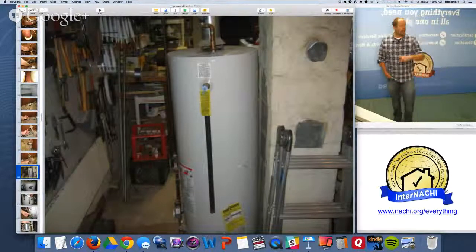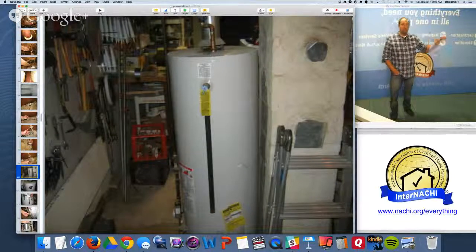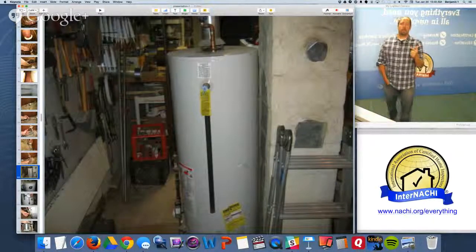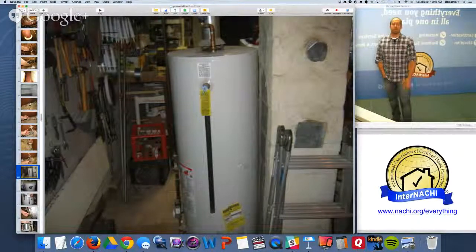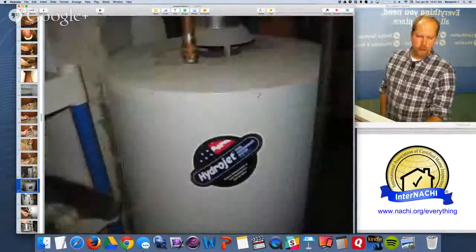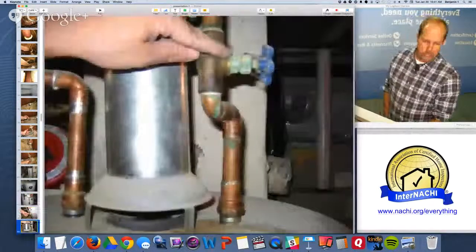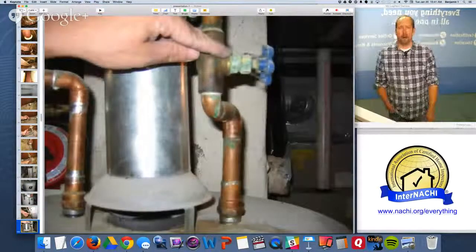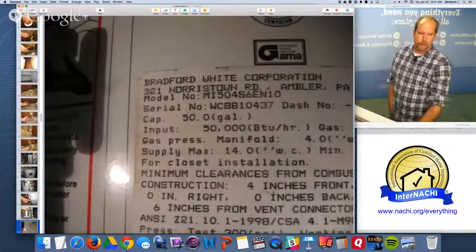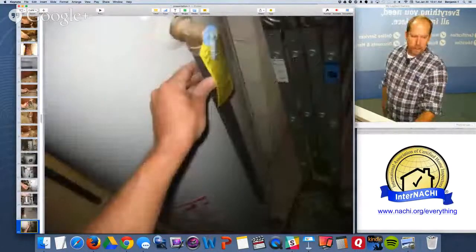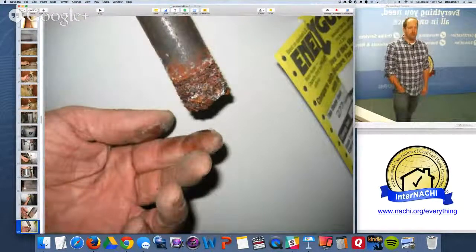There's the natural draft hot water tank, and there's the chimney. I take pictures of everything. I identify the size and the TPR valve — the temperature pressure relief valve — which is dripping at the end. So something is up with the TPR valve; it's leaking, and they had a nice little jar there to catch the leak. There's the flue pipe connection going into the masonry chimney. There is a clean out, so I stick my camera in and take a picture of the flue. No home inspector is required to inspect the interior flue liner of any chimney — metal, masonry, or otherwise — but I do it because oftentimes I see things: observed indications of defects.